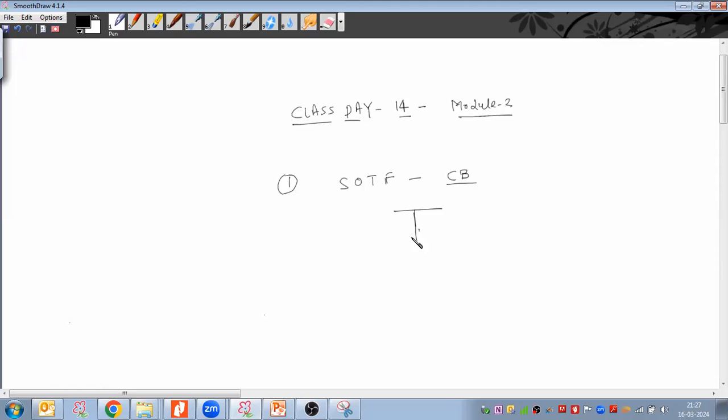Here I'm putting the isolator and CT, after that I'm putting the circuit breaker here, and thereafter we have an outgoing transmission line or outgoing feeder. And suppose this is my substation boundary here. So SOTF basically works within the substation boundary, right, Astikil? Yes, sir. Exactly, for that particular breaker, here, any fault happens.